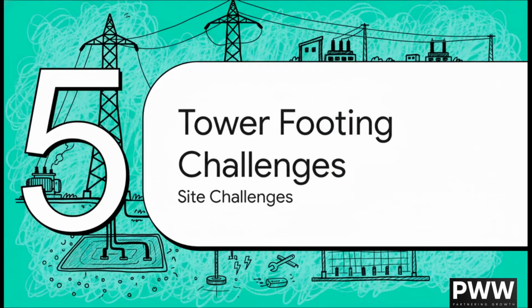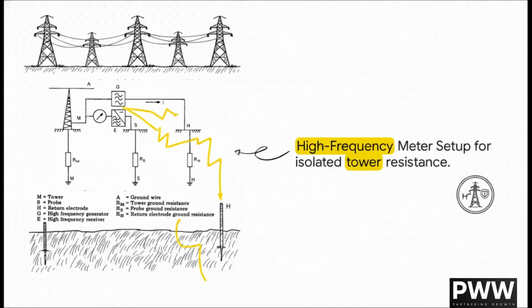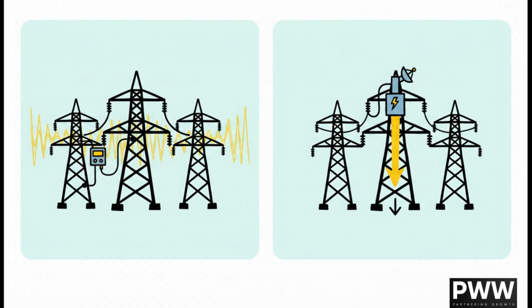Moving into Section 5, Tower footing and site challenges. And this brilliantly illustrates one of our biggest field headaches, testing transmission towers. Normally, transmission towers are all connected to one another by an overhead static ground wire. If you just hook up a standard tester to one leg, you aren't just testing that one tower, you're testing the entire transmission line. But specialized high-frequency meters use neutralizing circuits to electrically isolate the tower you are standing at, totally eliminating the need for you to physically climb up there and disconnect the static wire. It perfectly solves what we call the parallel path problem.